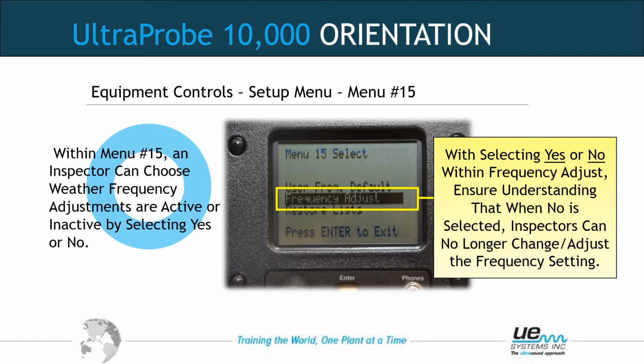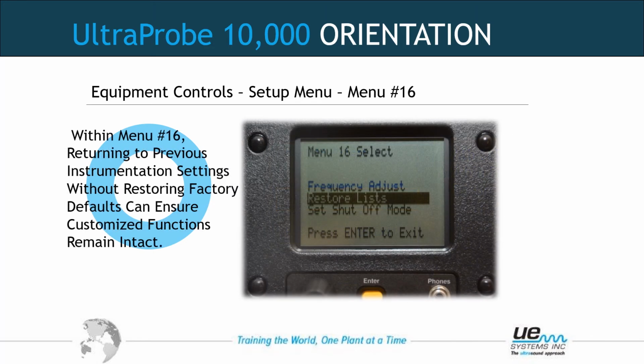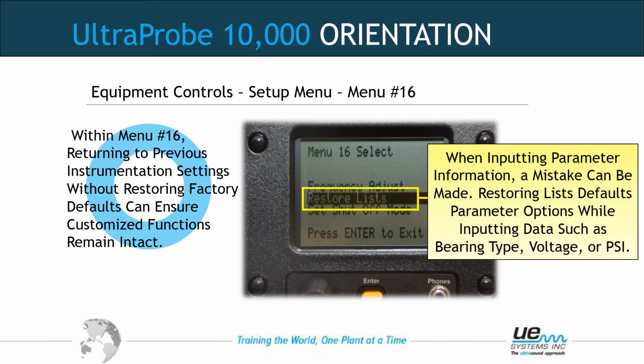Once back to the main menu, if you entered the frequency adjust area, rotate down to restore list. Restore list is the input data. You have drop-down options that you can choose what you want in there. For instance, for bearing, you have test result. What is your test result for the bearing? It's good, nothing. Maybe lubrication is an option. Maybe you want to pull out vibe. Maybe you want to pull out thermography. Maybe you want to pull out oil analysis as the next step. And you can put what those options are, and they will load to the gun from the software.